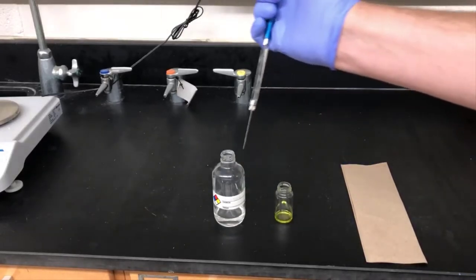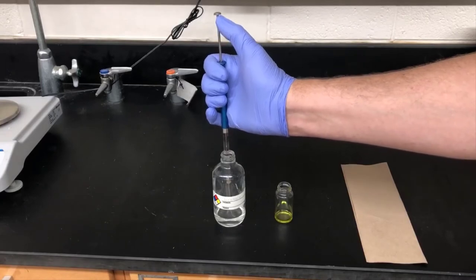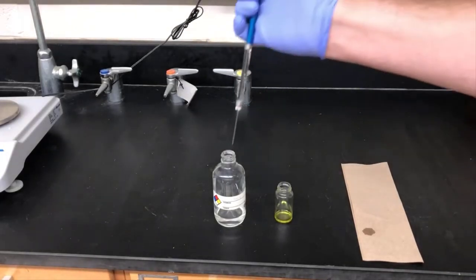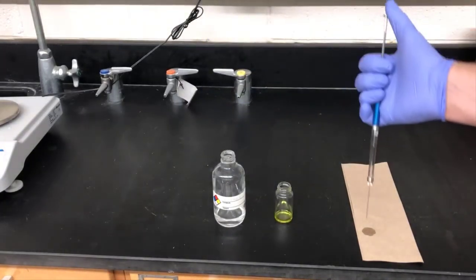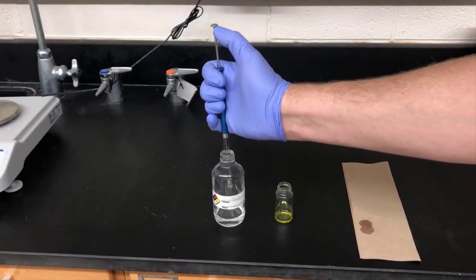I'll start by cleaning the syringe needle here by drawing up acetone and ejecting it out. I'll draw up a syringe full of acetone and then I'll eject it onto the paper towel. I'll do this three times. If you don't see a wet spot on the paper towel, it probably means the needle is clogged and it needs to either be unclogged or replaced.